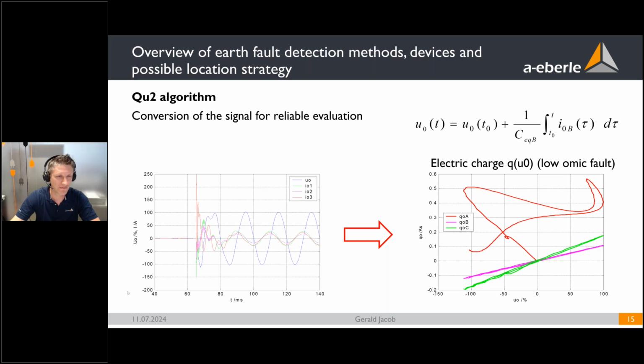On the left side, you see a diagram where at first, up to around 65 milliseconds, we have a healthy state, then the earth fault begins. We have transient behavior within the first round about 5 milliseconds, then it goes into a stationary state. The algorithm in the devices integrates the current over the voltage, over time, and in the end we get an electrical charge over the zero sequence voltage.